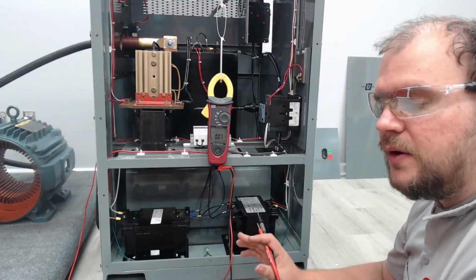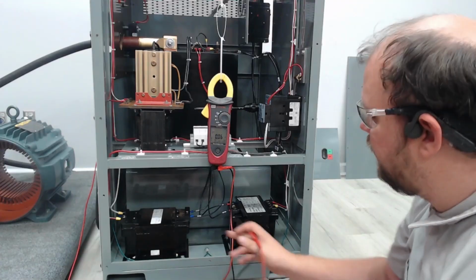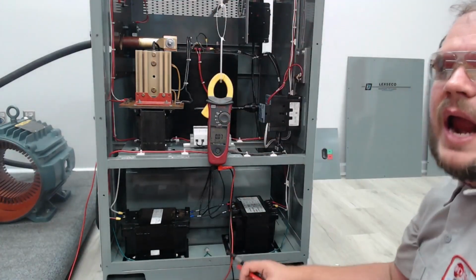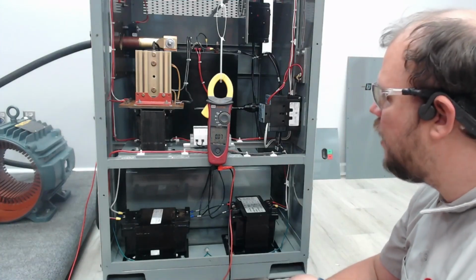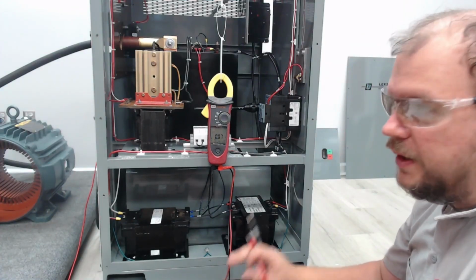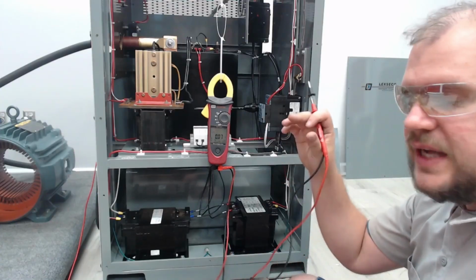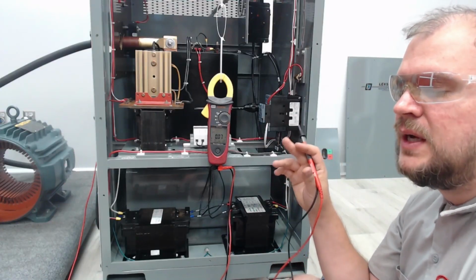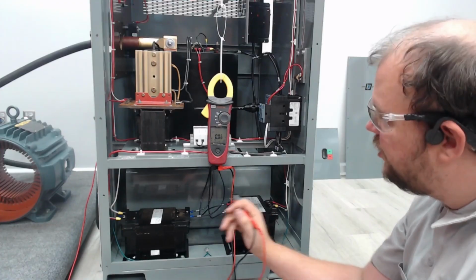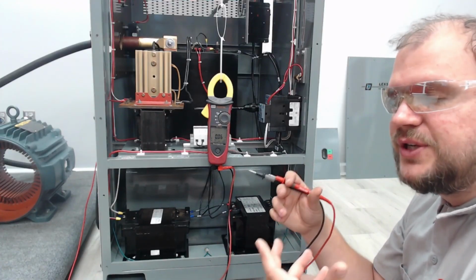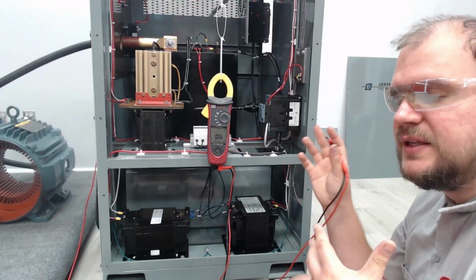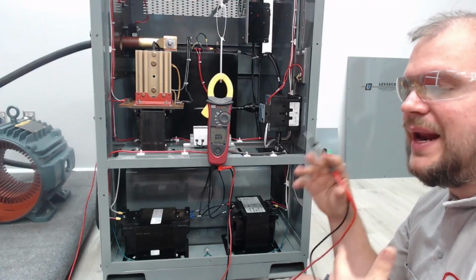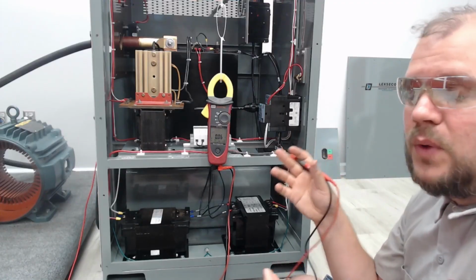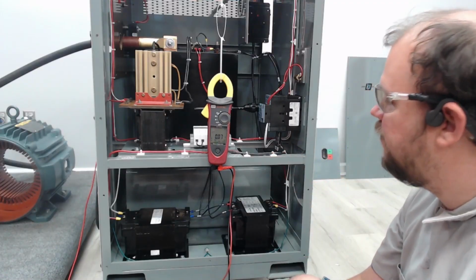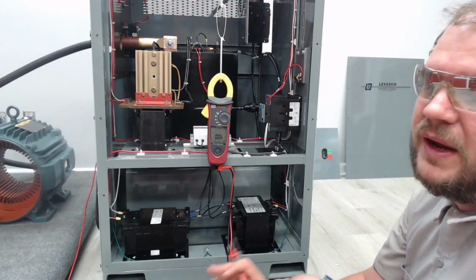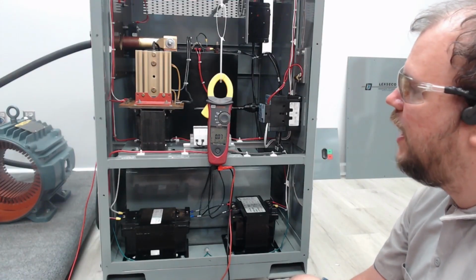If you have an upgrade or an older unit, unfortunately these transformers are probably going to be mounted on the side and you're going to have to reach in. I recommend using your phone, modern camera, whatever, to get in there, take some video, take some photos. That way you can read the information and already know where you need to touch and what you need to do. While the unit's off, you take this video, and that way you can look at it with your head out of the unit and not having to be upside down while you're trying to figure out where to touch. It is a lot more dangerous on the older units, so just be careful, get an extra hand, get whatever you need to do it safely.